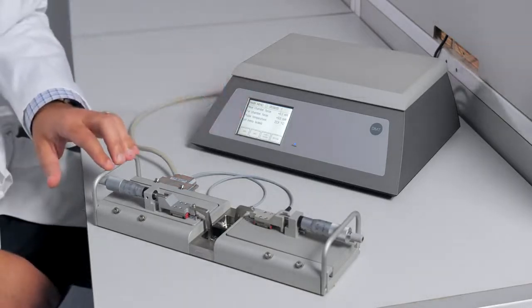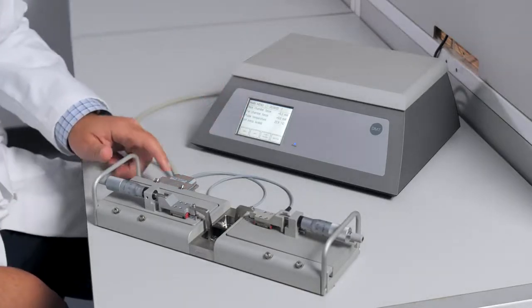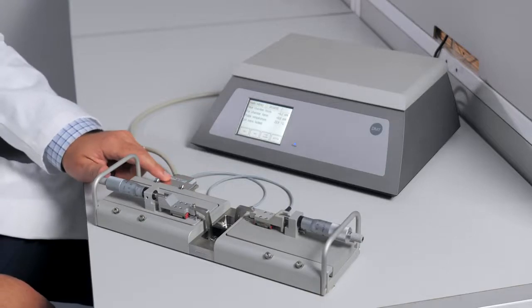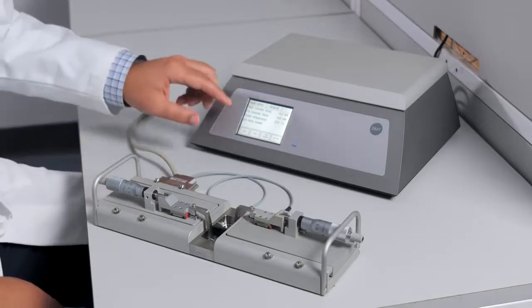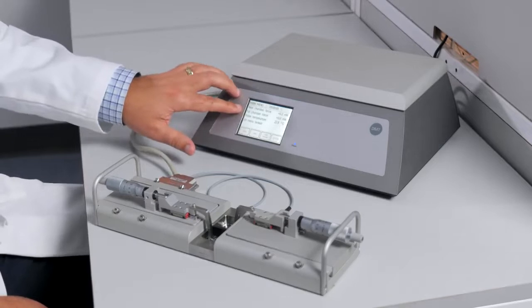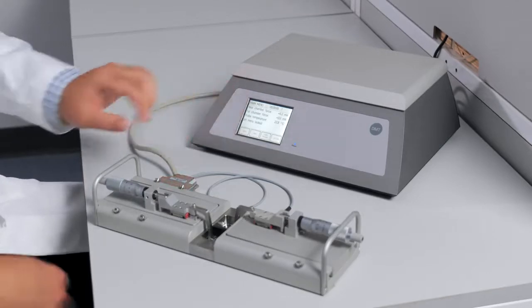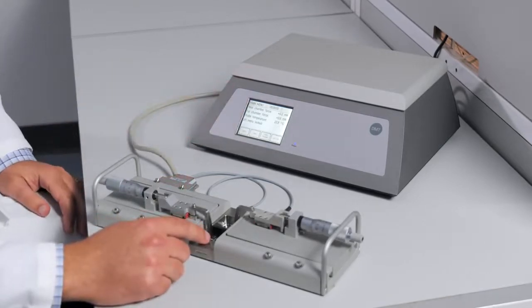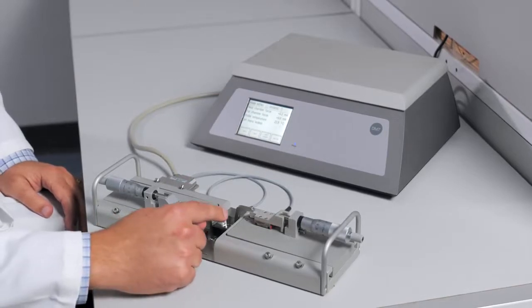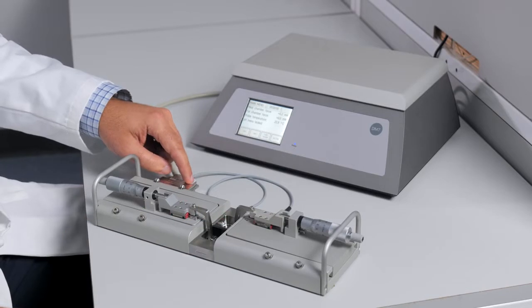When looking at the chamber itself, you will notice that the chamber is connected to the interface through the myograph cable. So to orient yourself with the near and the far force readings, the near reading is taken from the force transducer on the side that's closest to you, and the far reading is taken from the chamber that's closest to the myograph cable.